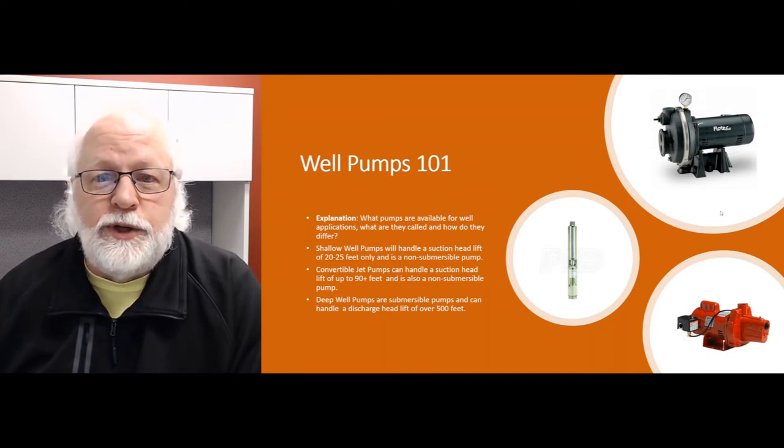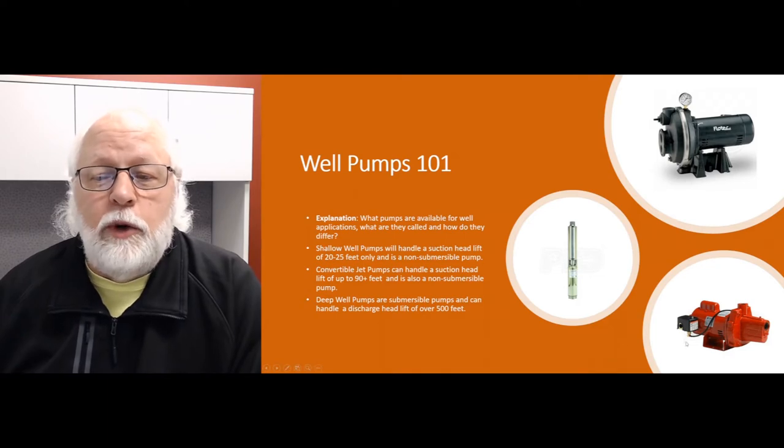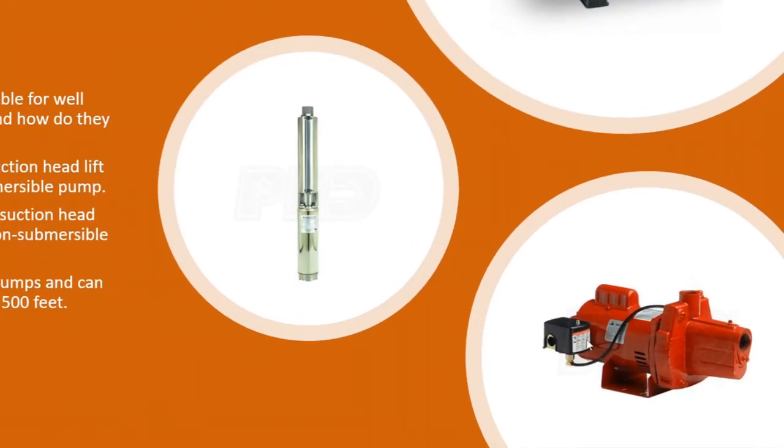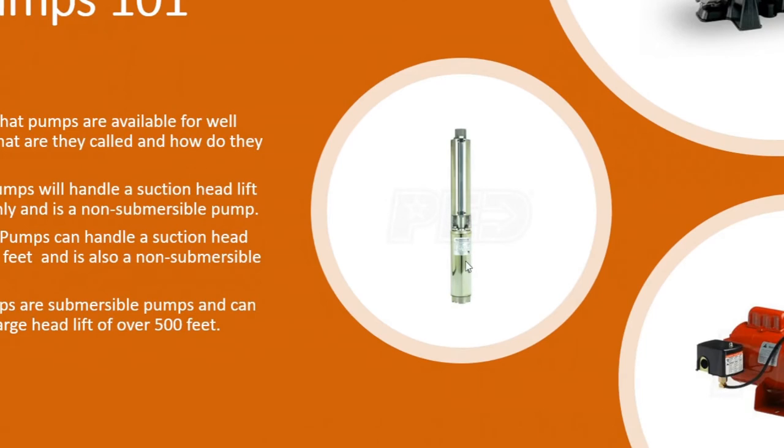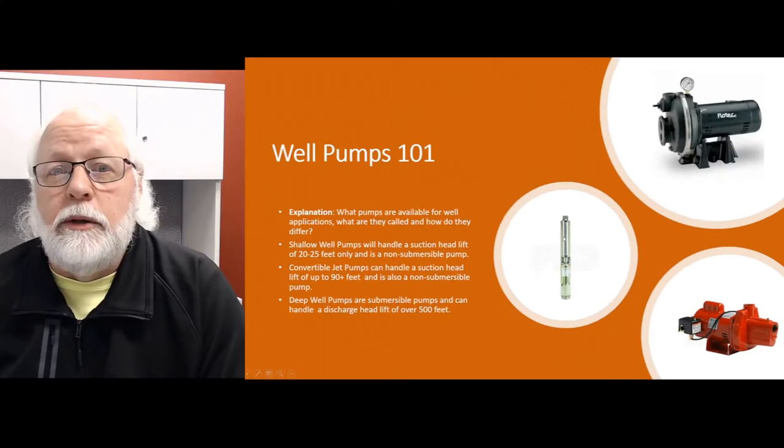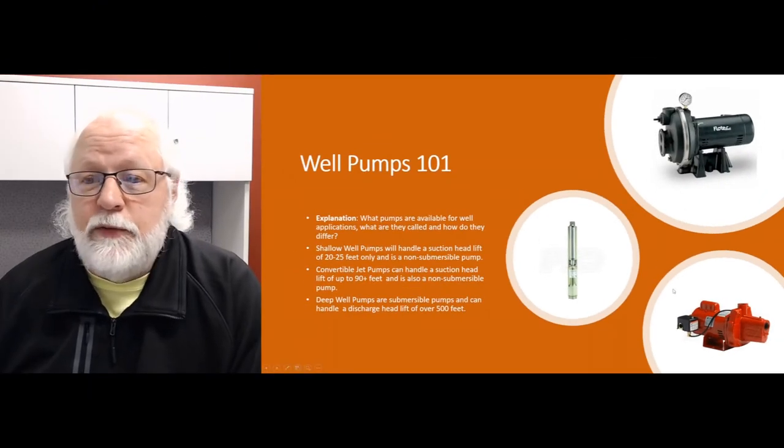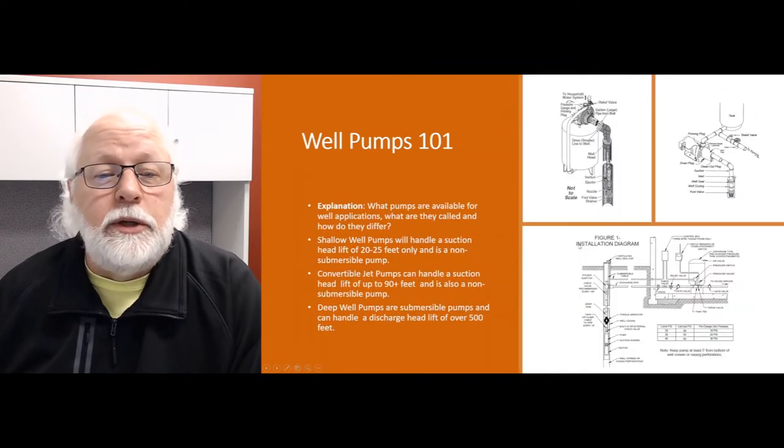What are their specific uses? You've got shallow well pumps that look very similar to the one on the bottom right here. These can handle a suction lift of up to 20 to 25 feet. Convertible jet pumps will handle a suction lift of up to about 25 to 90 feet, sometimes a little bit more. Deep well pumps are actually submerged in the well and in the water. They don't need suction lift because they're in the water, but they can discharge water well over 500 feet. That's really the main difference on these kinds of pumps.